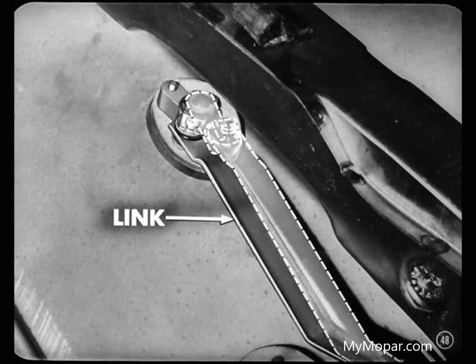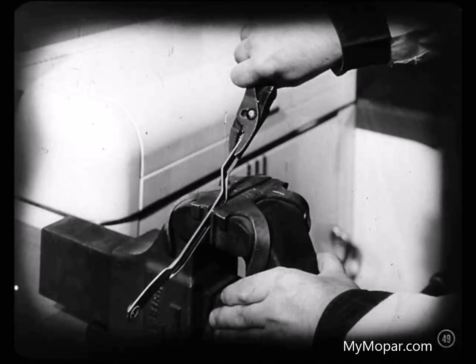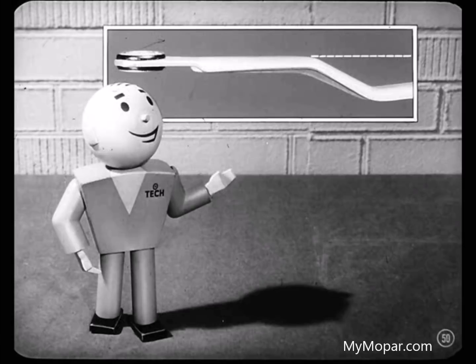Another condition is where the link is either too long or too short. This will cause the pivot crank arm to come too close to the over-center position. In fact, it can even go past center and stall the motor. Well, what do you do, Alex? Shorten or lengthen the link by increasing or decreasing the angle of the bends. But you want to be mighty careful to maintain your alignment of the link ends, so they'll slip on the pivots easy-like and operate through their arc without binding.